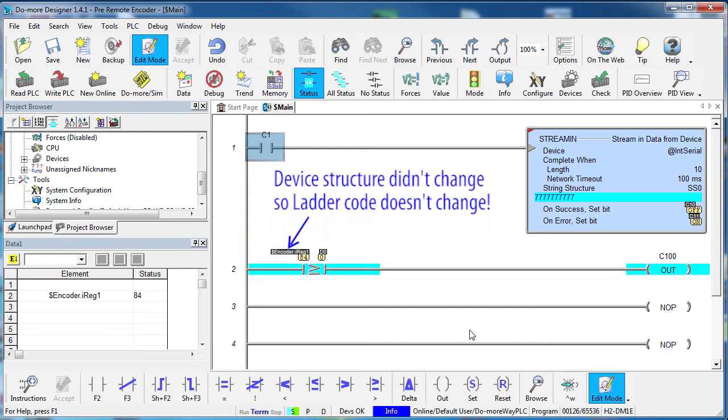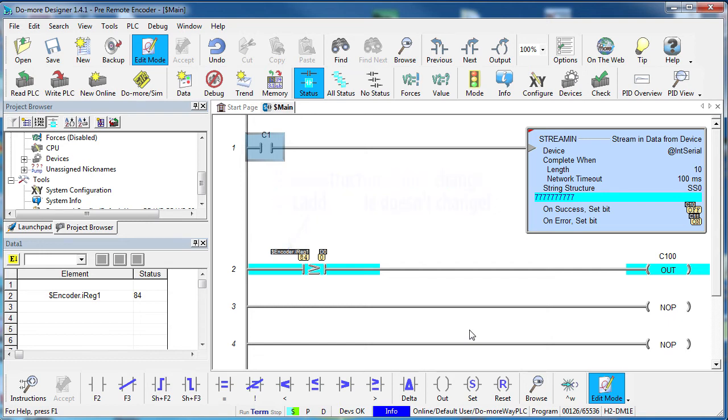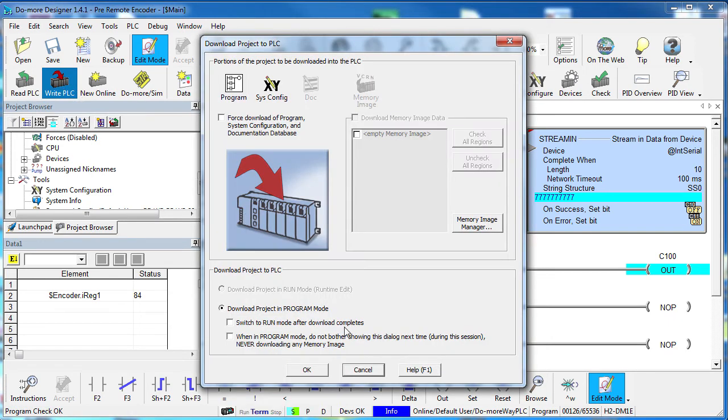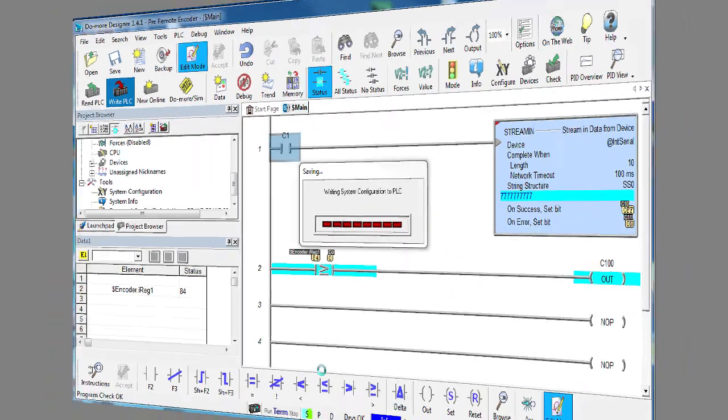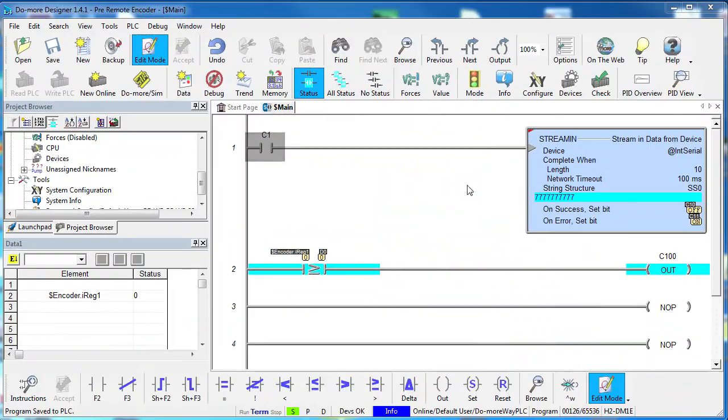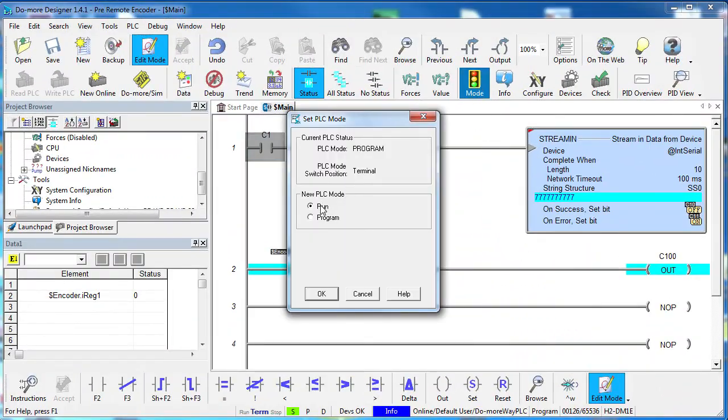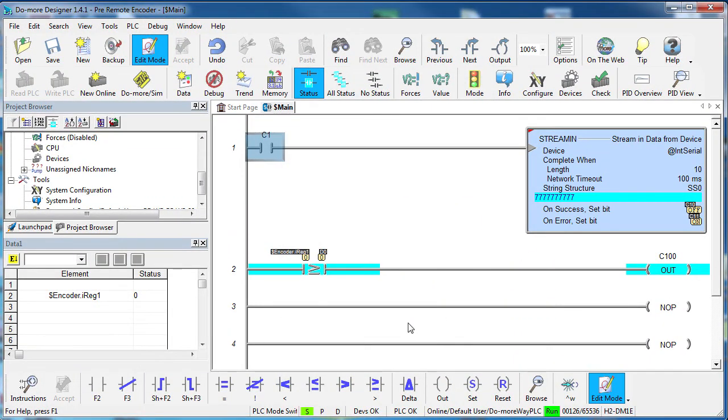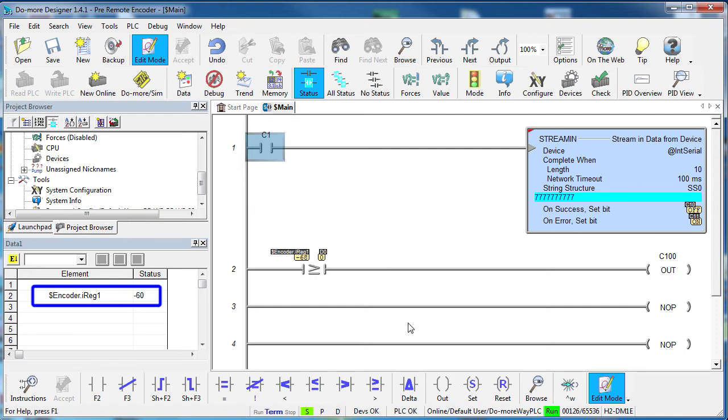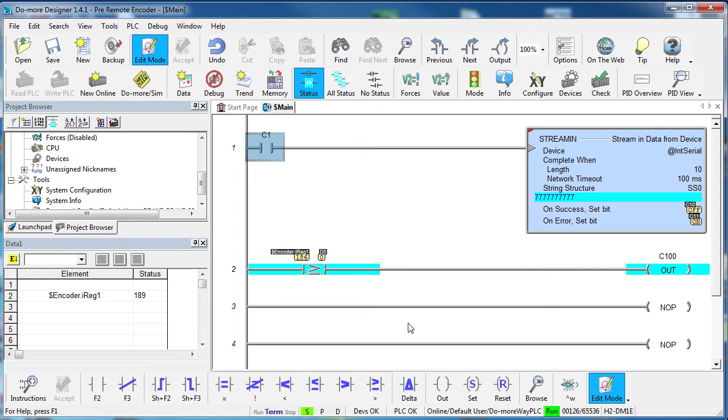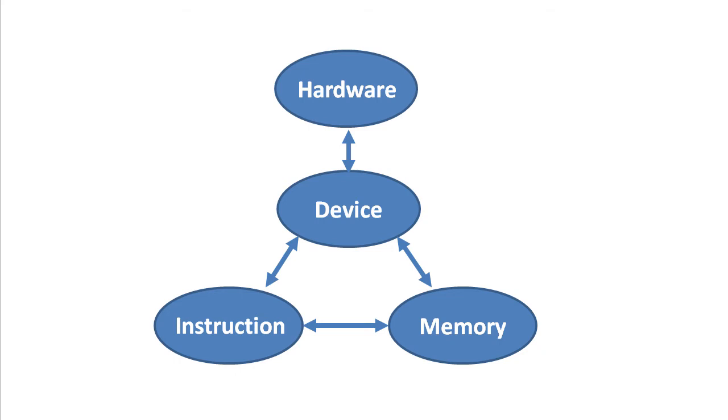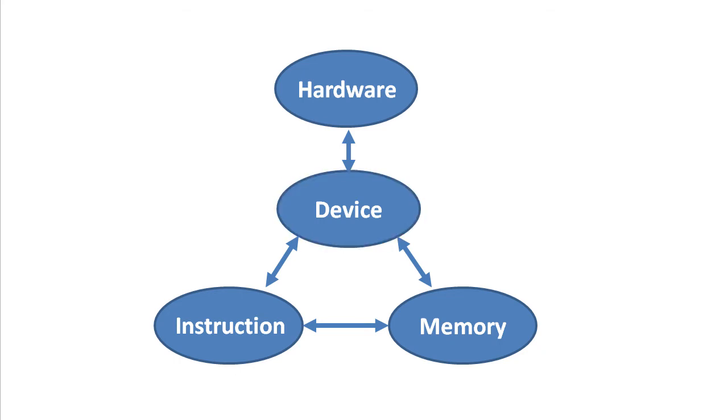Why? Because the ladder code still references the same device and the same structure. If we write this out to the PLC the error goes away, put the PLC in run mode and look, even the data view gives us the exact same result as before. It has no idea that we moved that entire module to a completely different rack.